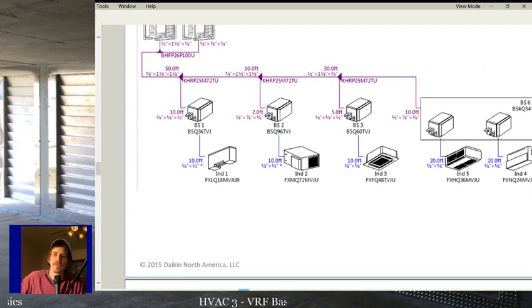Now, the other thing that I'll definitely ask you about is, what if you don't have a branch selector? On a heat recovery system, it is possible to run a unit without a branch selector. If you run a unit without a branch selector box, it can only be in one mode. It will only be able to work in one mode. And that mode is cooling, right? Because we always have a liquid line and we always have a suction line.